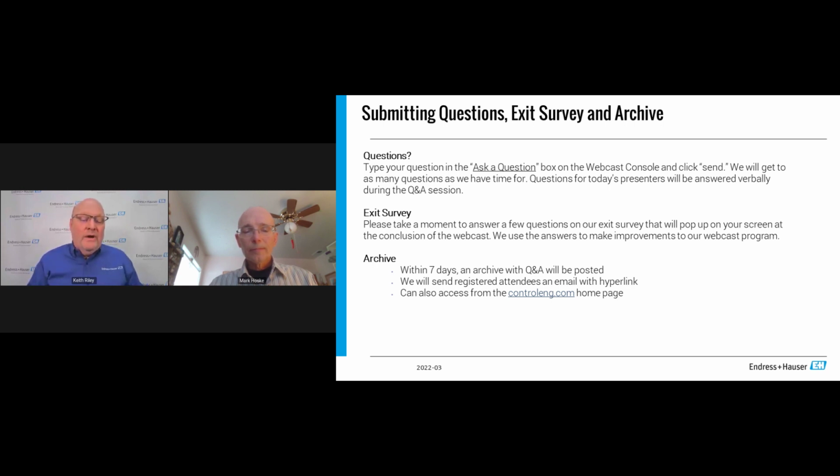Did they not wire it correctly, which means it's going to cause an issue with the measurement once you think you're back up and running. So the cost for me is all those things, and the downtime, when you're looking at several thousands of dollars each time you're going through some of those physical calibrations or other things, versus the very limited cost addition of a heartbeat verification and monitoring functionality. That's really what your comparison is at that point.